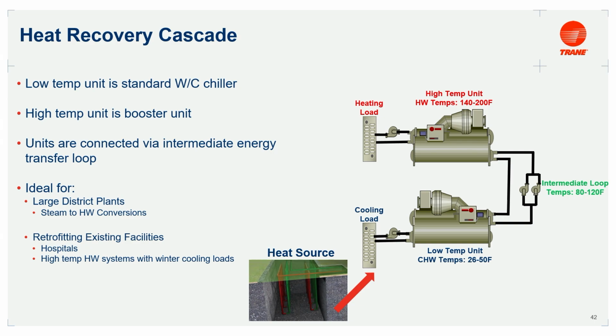We can drive a COP at worst at about 150 degrees of lift and about 3.5 on heating only, not even considering the simultaneous. So another unique application might be dual temp systems, right? Maybe we want a decentralized cascade. Let's put 120 out to all the buildings that can handle it. But we've got 3 or 4 buildings where there's nothing we can do. It's a massive cost overhaul. Let's put a booster in the basement of that and boost that up to our 180-degree water. Maybe we don't need the whole plant to be 180. Maybe it's just in an individual building. Let's boost the certain areas that need that 180 and let everything else run at 120.